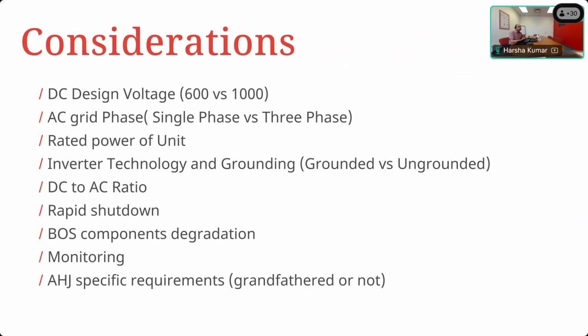In addition to that, rapid shutdown. Back in the day, you did not need rapid shutdown. So if the authority having jurisdiction is willing to grandfather you into the new system with the new inverter, that's fine. If not, you might have to take that into consideration. Outside of this, you have the balance of system components. If you've got any switches, fuses, protection equipment, all of those will degrade. So you have to make sure that they are actually functioning like they should be before you decide to trust them. Okay. Outside of this, monitoring.